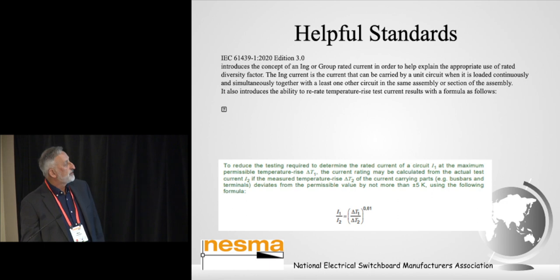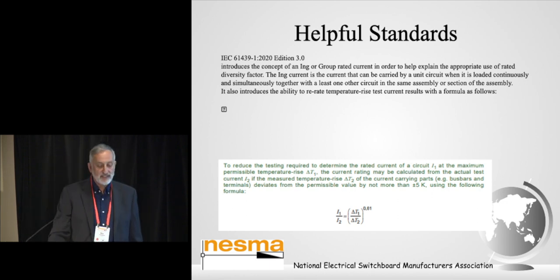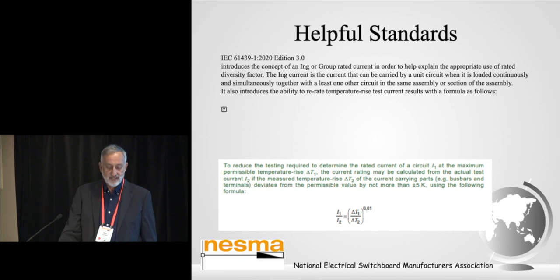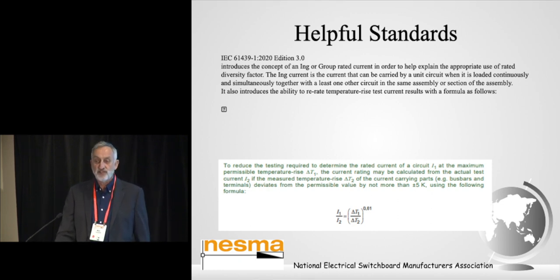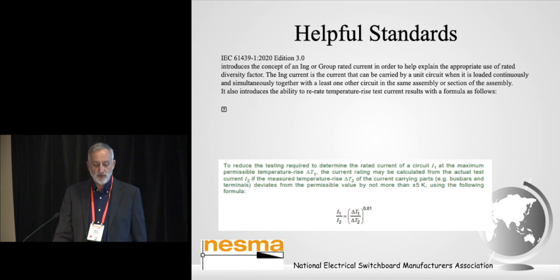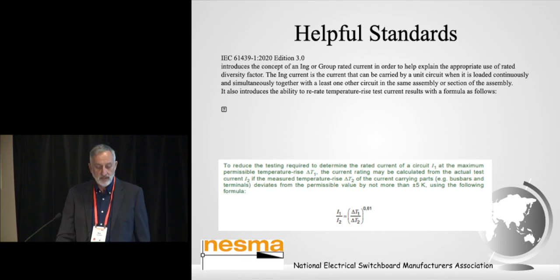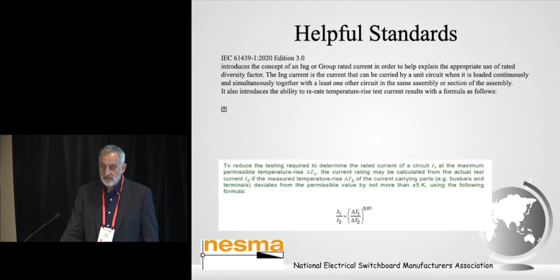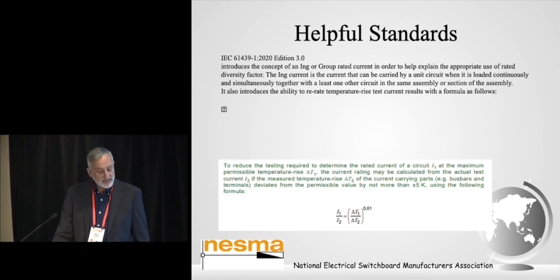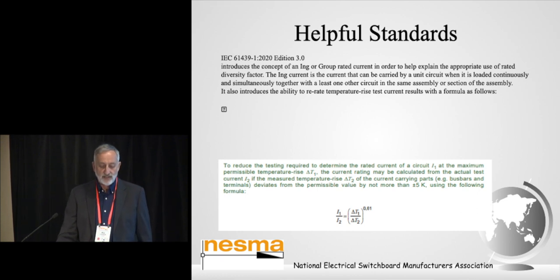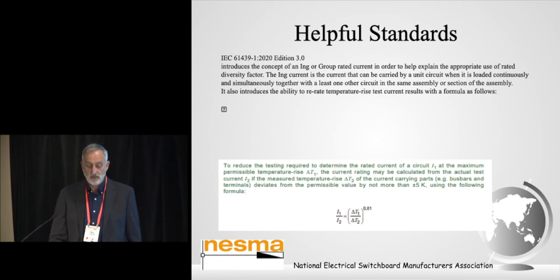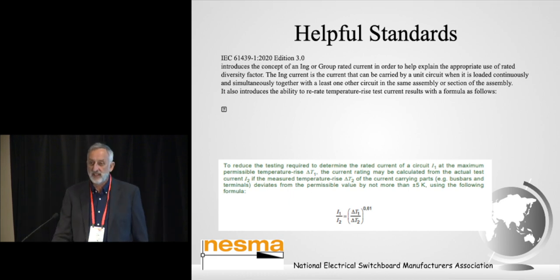So other helpful standards that can be used: the IEC, which is not adopted by Australia as yet, edition 3, introduces the concept of an InG, or a group rated current, in order to help explain the appropriate use of rated diversity factor. The InG current is the current that can be carried by a unit circuit when it's loaded continuously and simultaneously together with at least one other unit or circuit in the same assembly or section of assembly. So what we're getting is the rating of the particular unit being affected by mutual heating from units alongside.